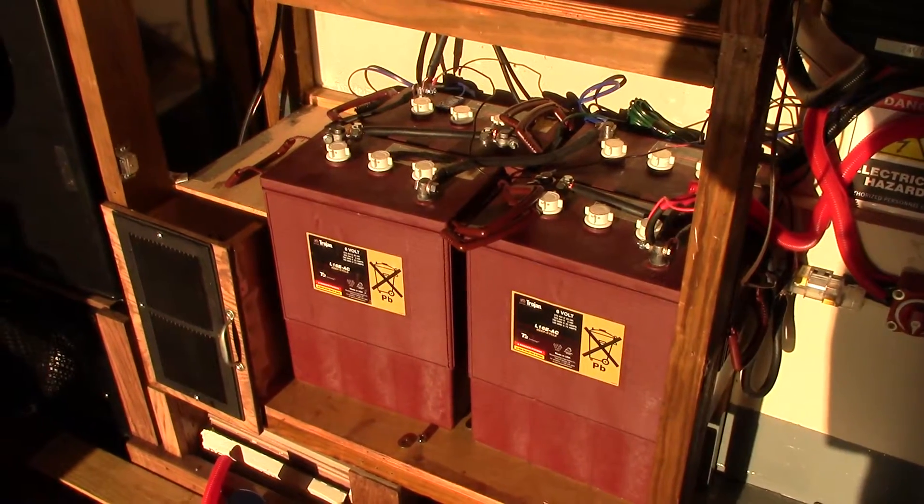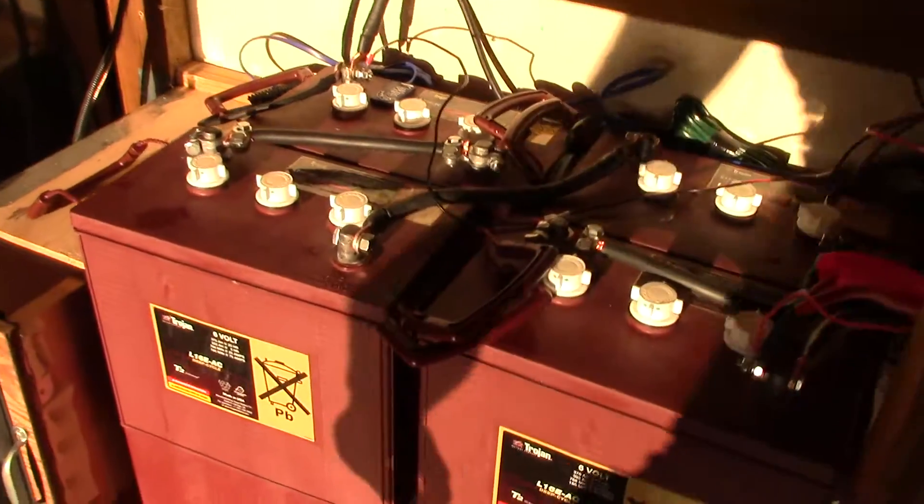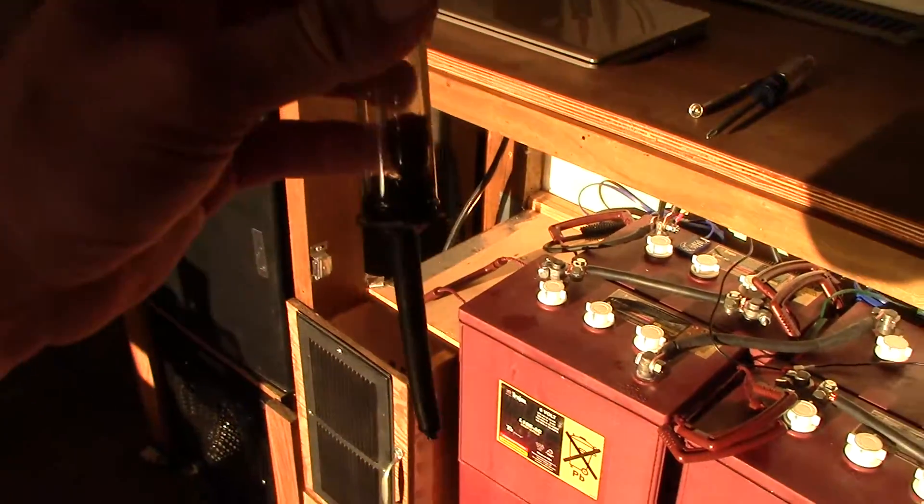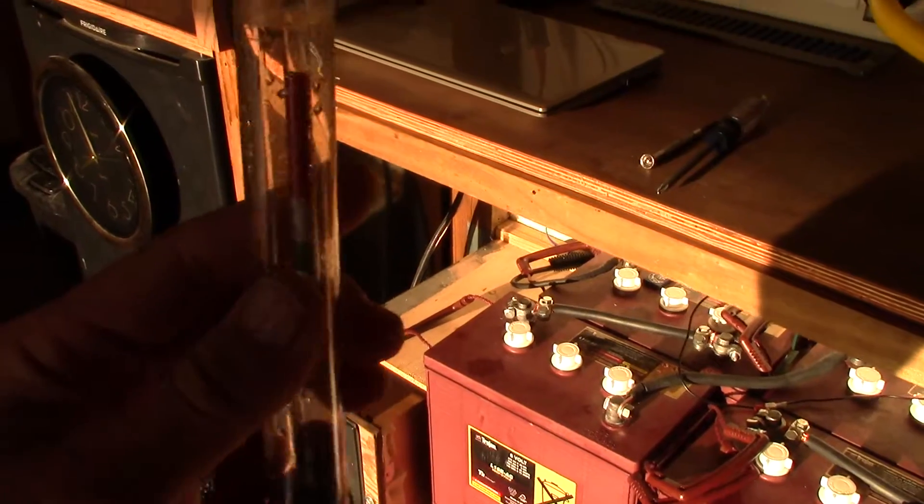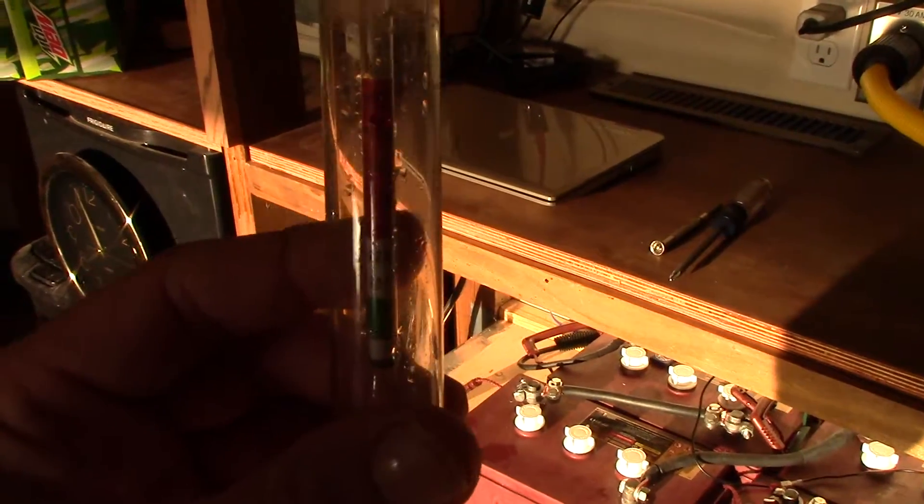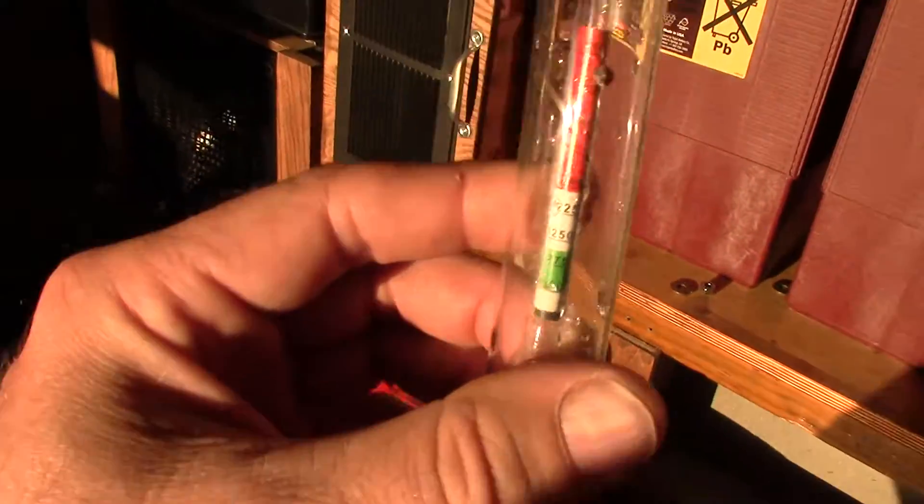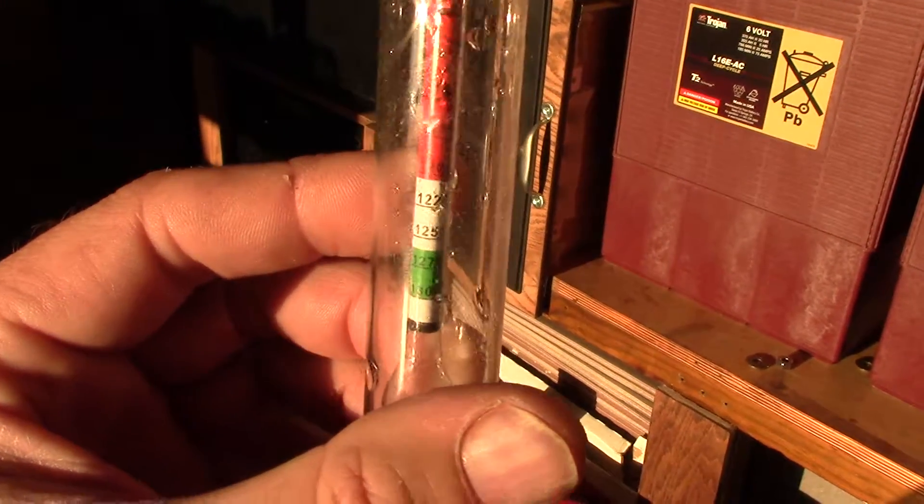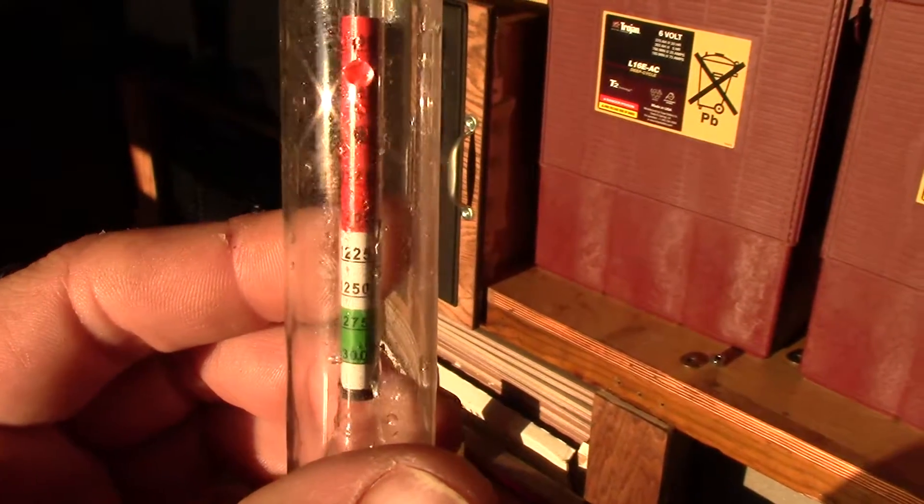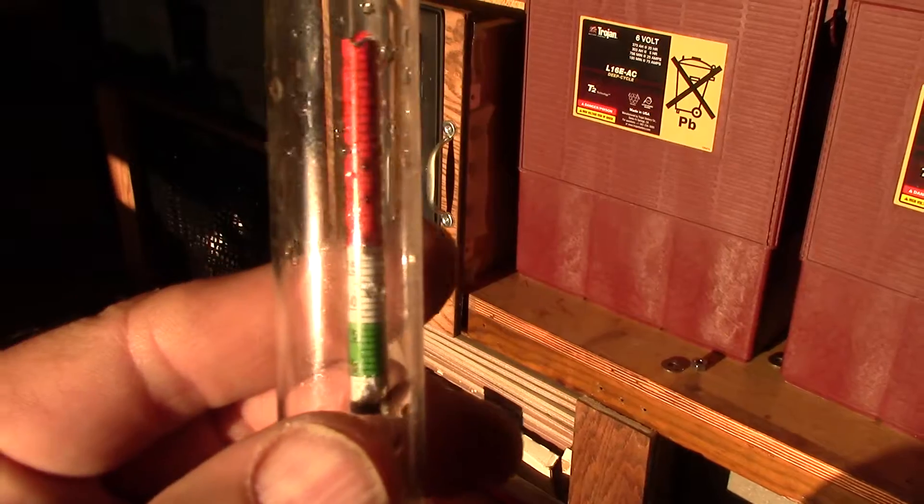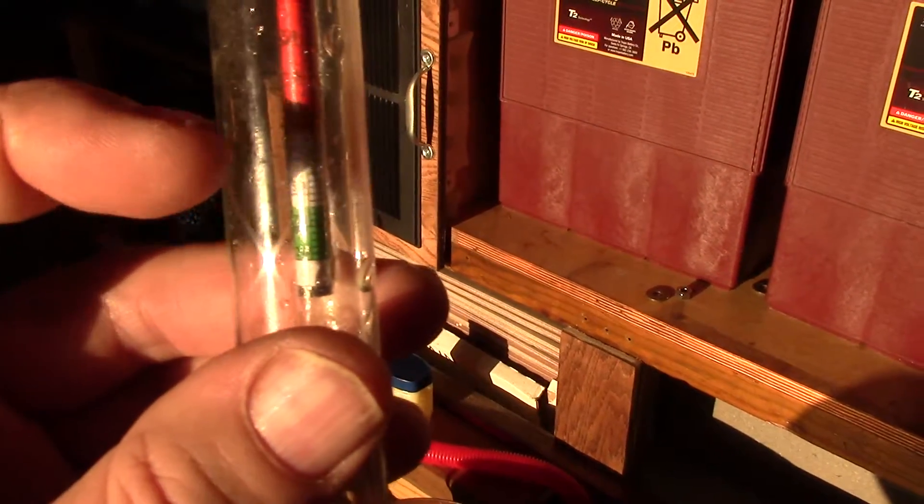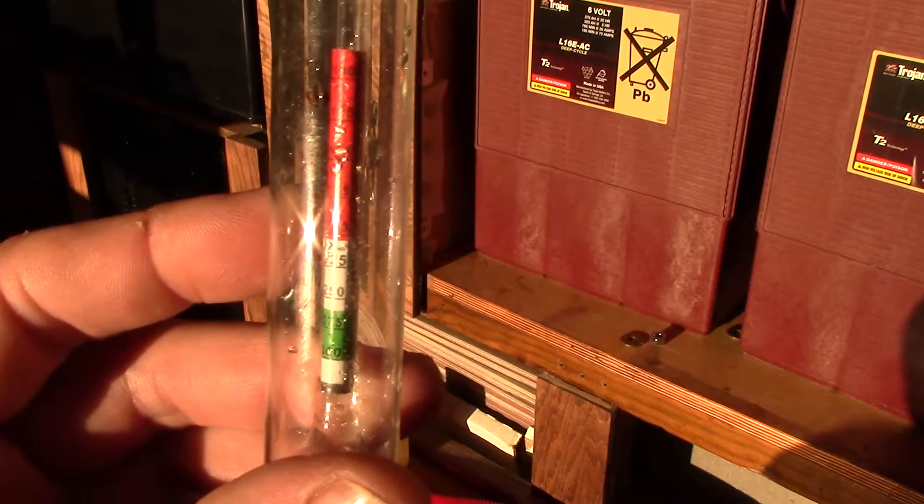To make sure everything's good, check the specific gravity. I did a little bit of testing last night. I don't know if you can see this, but they're at 1.225—fair condition in the white right there.